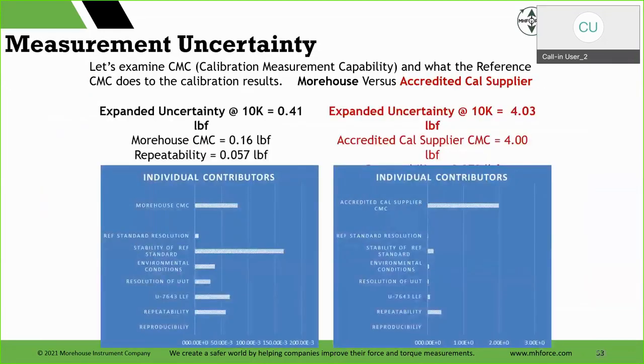Let me try to show it a different way, graphically. You have a 10,000 pound load cell. Morehouse does the cal: 0.41 expanded uncertainty, Morehouse CMC, 0.16 repeatability. When the accredited cal supplier does it, they're at 4.03, and then their CMC is 4 pounds at that. Just look at it and let it sink in.